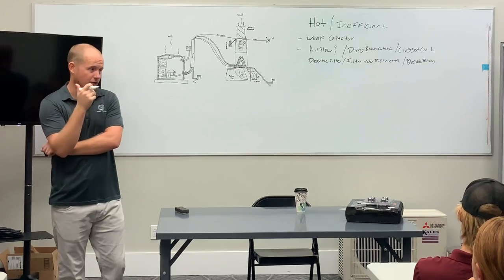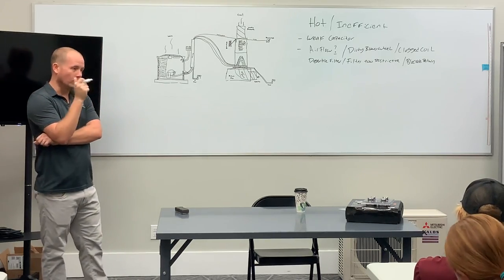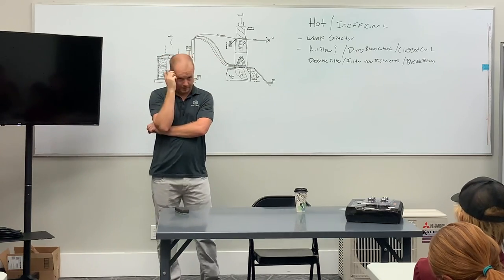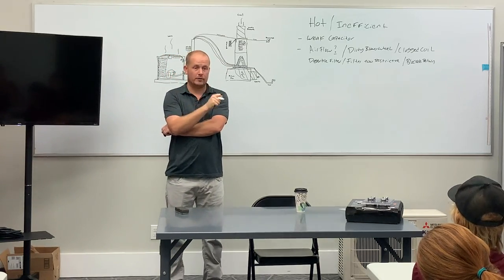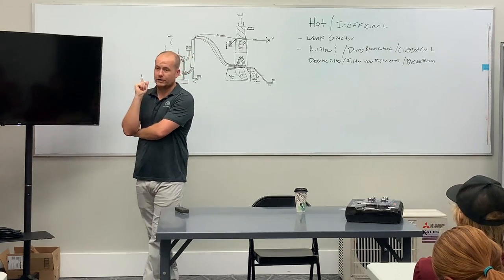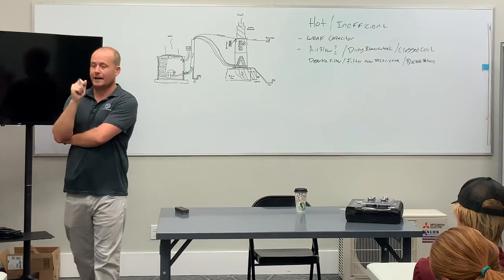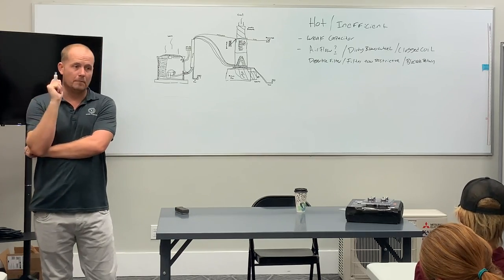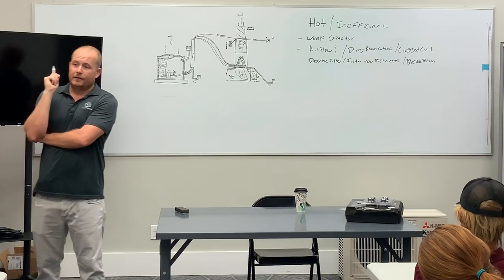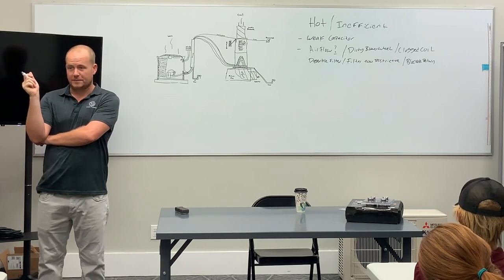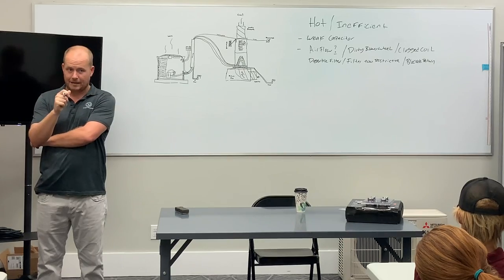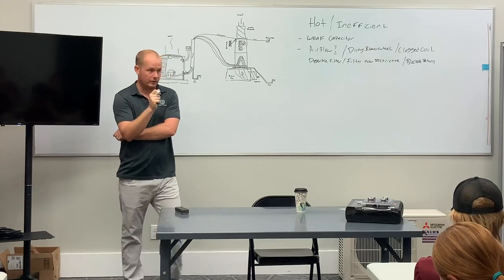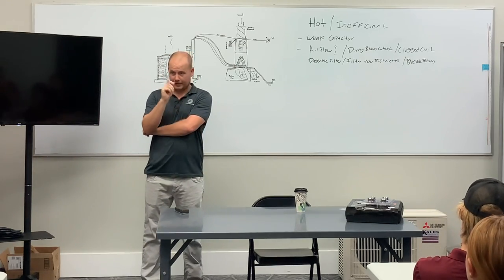Lower current. It draws lower current. So if you take an old school air handler, old school furnace, and you put a dirty filter in it, and you're monitoring the current of that motor, it will actually draw lower current, because that motor, that blade design, is loaded based on airflow, meaning how many cubic feet of air, or more specifically how many pounds of air, that motor is moving, not by static pressure. So when the static pressure goes up, that motor is not working harder. It's working less hard. We're talking an old school motor.